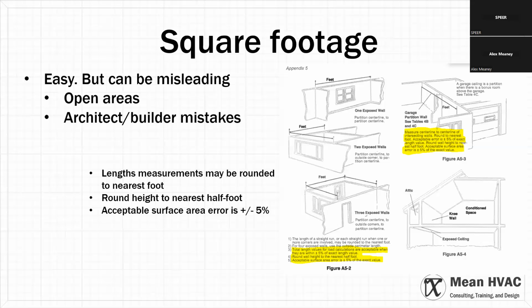They often get stuck on not matching the square footage of the plan exactly. That's not a requirement. Straight up, that's a made up thing. You do not have to match the square footage of the plan exactly. This is load calculations, right? We're not doing structural - structural I need to be pretty exact. In load calcs, especially for surfaces that are well insulated, plus or minus a bit is not much.